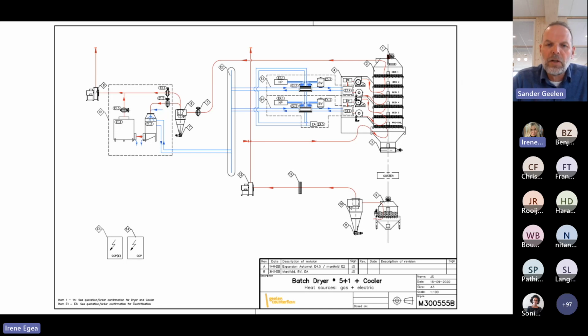But the blue lines are relatively new in our electrical dryer. And on the left-hand side, what you see is what we call a counterflow recovery unit. So we first start by condensing that air which comes out of the dryer, because it contains all the latent heat from the evaporation of water out of the product. And what we want to do is to condense that air as quickly as possible in a relatively short time frame, so we recover very efficiently the latent heat. And we can recover in that particular location between 65 and 75% of the energy which is contained in the top of the dryer. However, it comes out at a relatively low temperature. So there is 40 degrees Celsius, roughly, water coming out of that energy recovery unit.